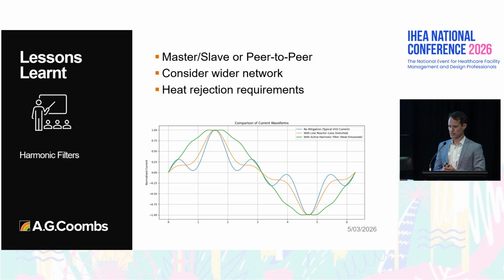So, as I said, we had 2 harmonic filters that were being installed on this job. Due to the HV project and the implications of that, the intent was originally that each mechanical switchboard was fed from a different transformer, so each harmonic filter was on a different low voltage network. That didn't end up being the case for a period of time. We had the 2 harmonic filters connected to the same LV network, and these filters can operate in parallel, but they need to be set up that way.